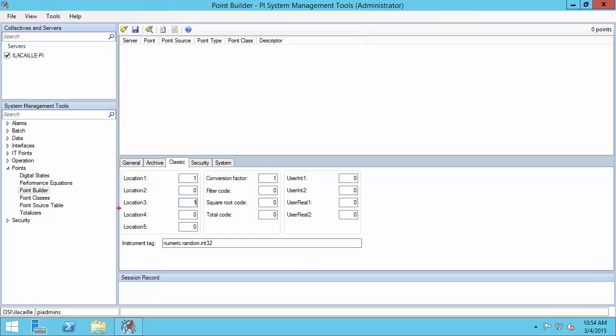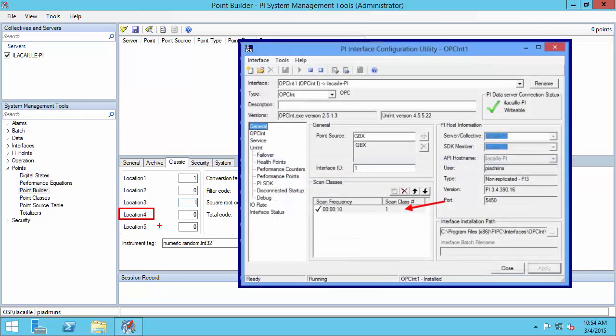Location 4 is where I'm going to specify which scan class my PI point belongs to. Remember the rules: only advise points can go into scan class 1, and never mix input points of different types in the same scan class — for example, you can never put polled and advise points in the same scan class. Since my input point is advise, I can choose Location 4 of 1.